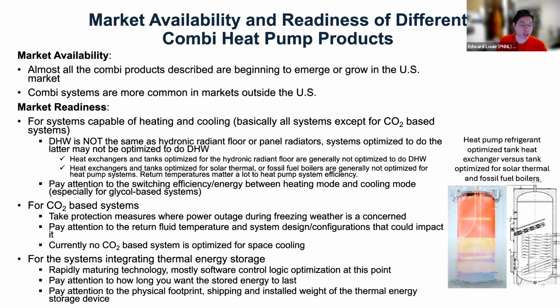For CO2-based systems, something to note is if you live in a location where you may experience prolonged power outages during freezing weather, then take precautions, like maybe a backup battery or something like that, because if you have potable water that has no glycol in it going to the outside, you could potentially freeze and blow up a heat exchanger. And these systems are very sensitive to return fluid temperature. So in your system design, make sure that you're not returning high temperature fluid back to a CO2-based heat pump.